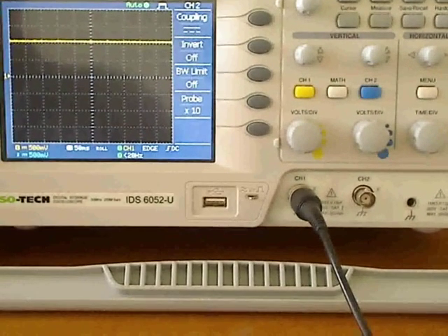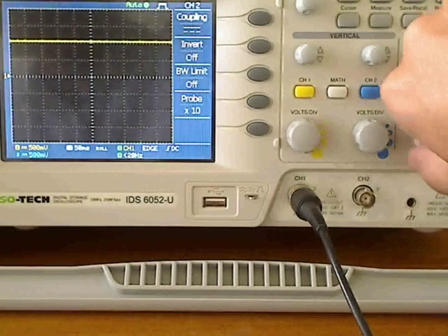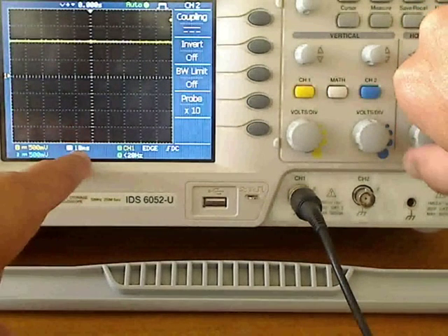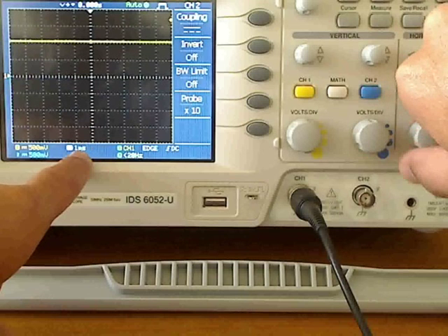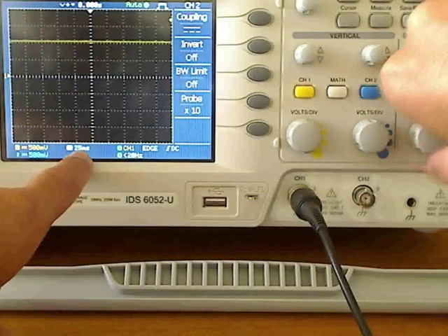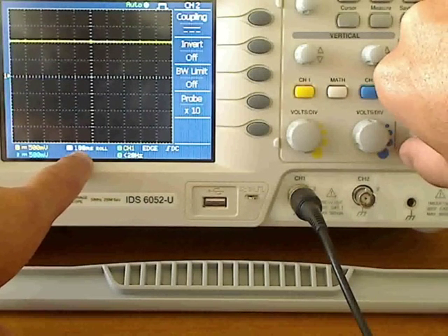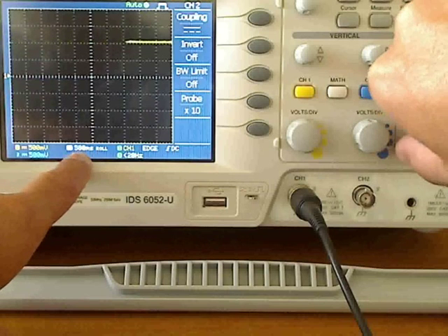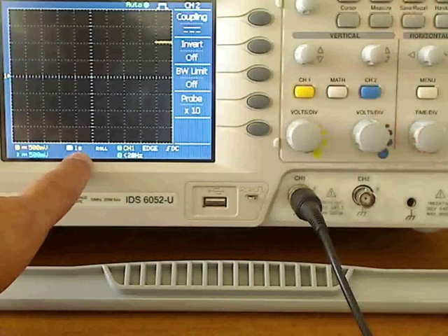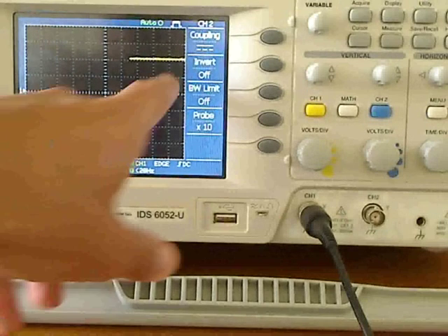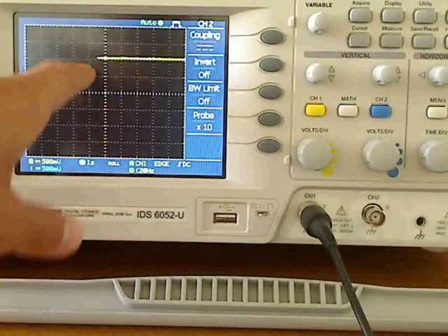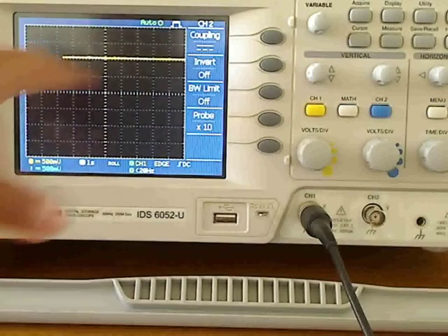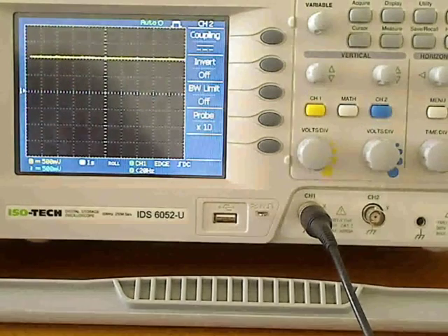So if I just move back slightly here and turn this knob, you should see that this tells you each block is now 1 millisecond. If I turn it to the left, each block is 100 milliseconds. So you can zoom in and out. If I go to each block is 1 second, you can see that it takes about a second to cross one block. It's 1 second, 2 seconds, 3 seconds. So this thing is really sampling quite slow now. So I'm just going to make it a bit faster again.